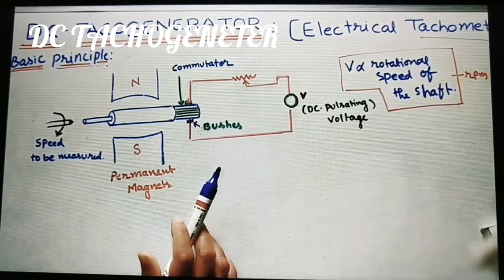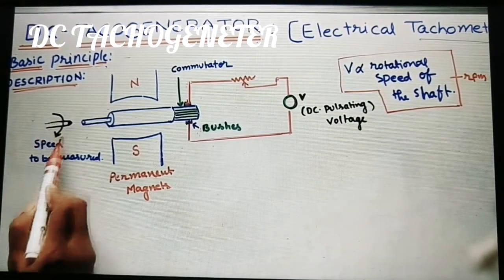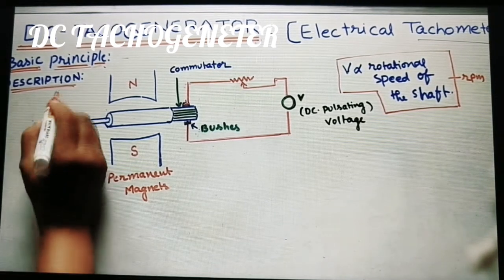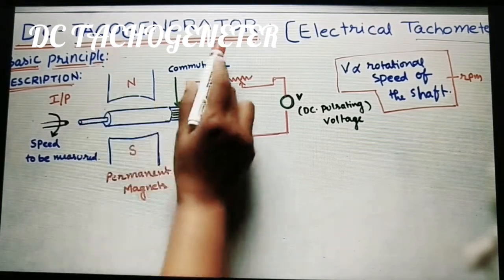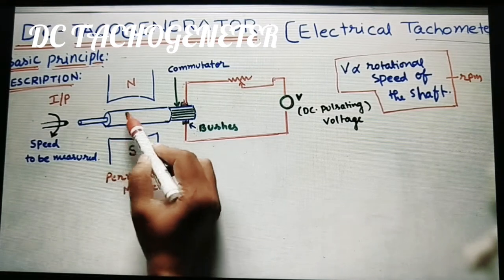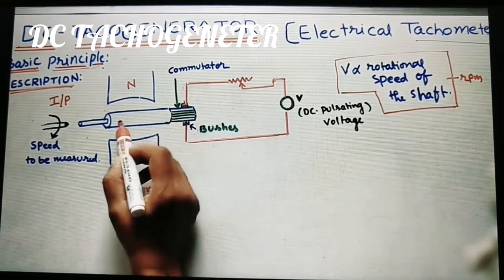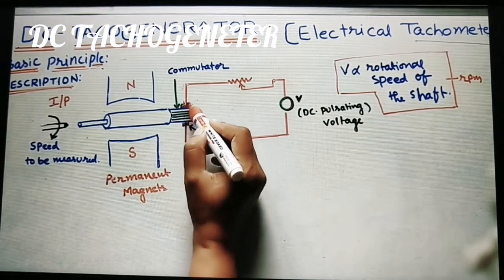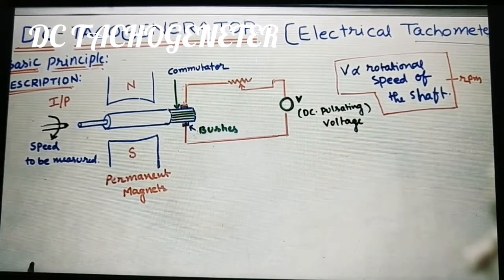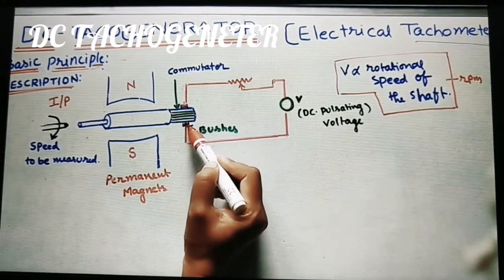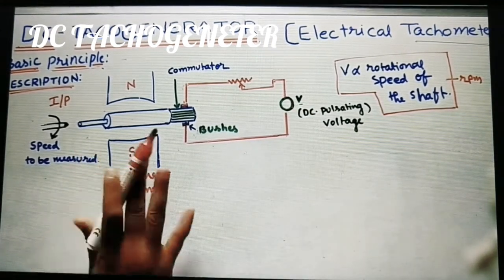Now let us look at the description of this tacho generator. The input shaft is the machine shaft or engine shaft whose speed is to be measured, and it is connected to the tacho generator. The main parts inside are: the conductor — an electrical winding — and two permanent magnets, North Pole and South Pole. Whatever electricity is generated is collected by brushes, which are brush-type contacts touching the commutator. The generated voltage is then read on a voltmeter connected to the output.